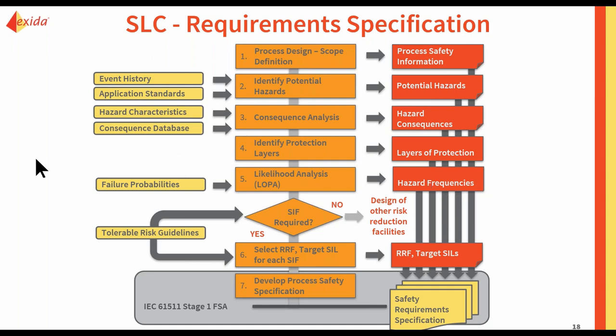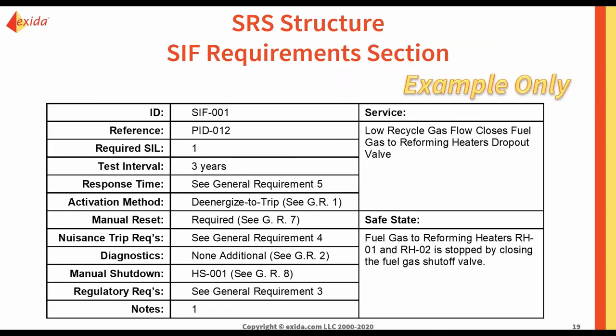And this would be a very simple example of an SRS. For an SRS, usually we would see things like the test intervals, the response times for them, and most importantly, the service, which is the action for the SIF, and also the safe state, which defines when the SIF is completing its action in a way that is going to bring the operation back to a safe situation.